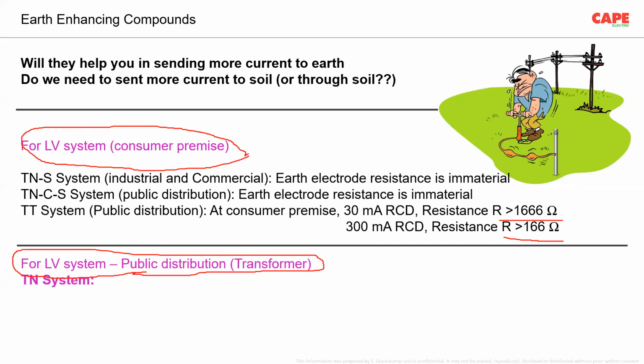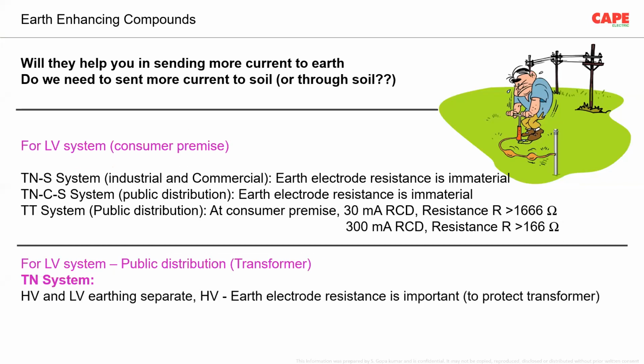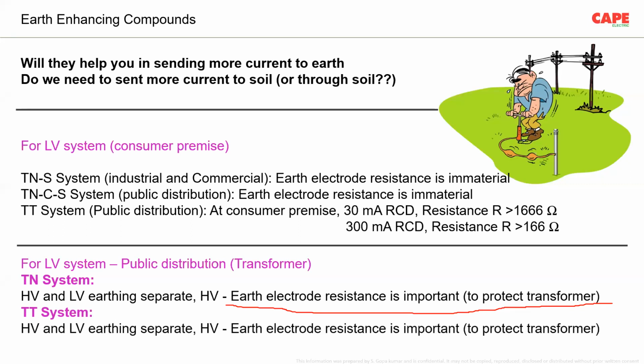If they go for a TN system, and if they go for HV and LV earthing separate, that means the transformer HT side and the neutral earthing separate, then high voltage side earth electrode resistance is important to protect the transformer. Otherwise, the transfer potential during a fault at the HT side of the transformer may kill the LT winding. So for the public distribution company, sometimes if they go for HV and LV earthing separate, then the HV earth electrode resistance is important. In case of a TT system, again for the public distribution company, if they go for HV and LV earthing separate, the HV earth electrode resistance is important to protect the transformer.